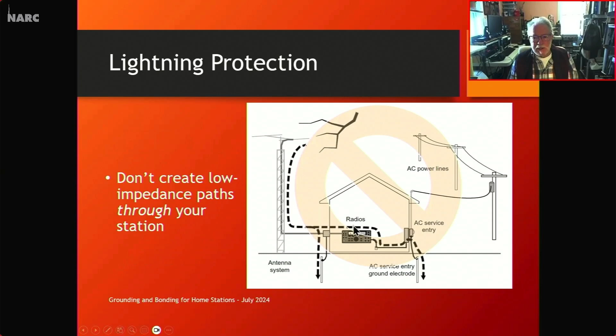So everything's grounded, your tower, your entry panel, your AC power system, and every one of these ground rods, every 10 to 20 feet, is bonded together with this buried wire here, and that gets over to your AC service entrance. So if Mr. Lightning hits the power lines, for example, and comes in on your power service, and it says, okay, some of me is going to flow along this ground connection to a ground rod here. And some of it's going to go through this unprotected AC circuit. But if you've got your AC power protected on that panel, then most of the current is going to go out to the earth electrode the way you want it and not through your radios.